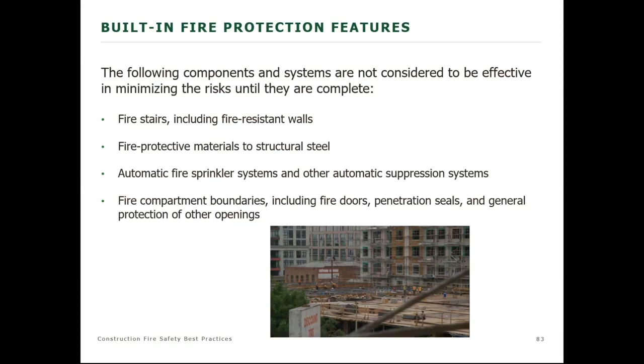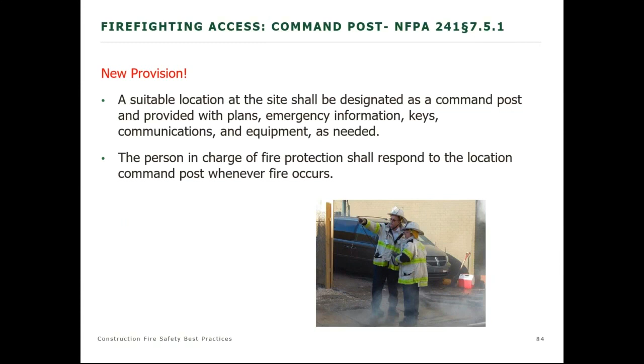Now, there is a new provision in NFPA 241 that says during construction, a suitable location has to be designated for the command post. And it's supposed to have plans in there, emergency info, keys, anything that you need should be in there. And the person in charge of fire protection for the site should know to respond to that location if an emergency occurs. Yeah, so it's a key box provision. If you lock anything down, you have to have a key box. That's an example of a Knox box, and all the keys to get access to all areas of the construction site have to be in there.